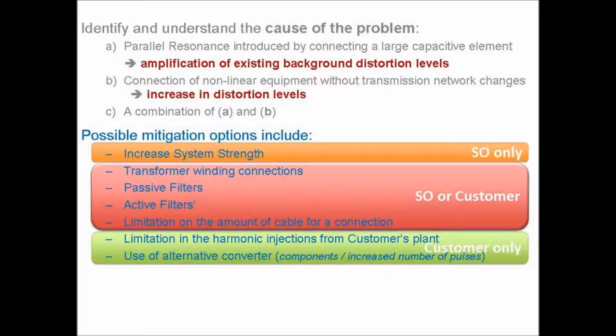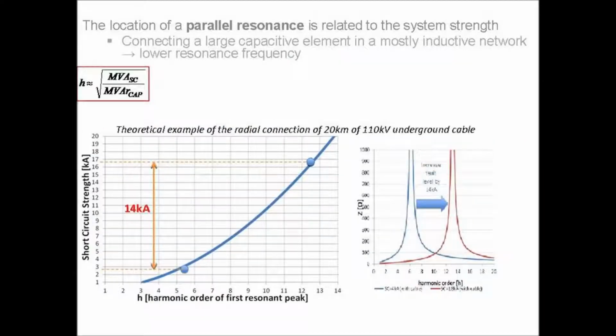So the first one of those, the increase in system strength, is purely a system operator kind of step. There's not much you can do about it in your wind farm. The next ones, I suppose, are all either system operator or customer. Anybody can change or decide on transformers or different filters, and limit an amount of cable. That's up to you, but it could come back to Eirgrid or the ESB networks and say, no, we can't accommodate that. It's just not going to be feasible. And then the last one is customer only. Like only you can pick your turbines, and only you can make sure that they're compliant.